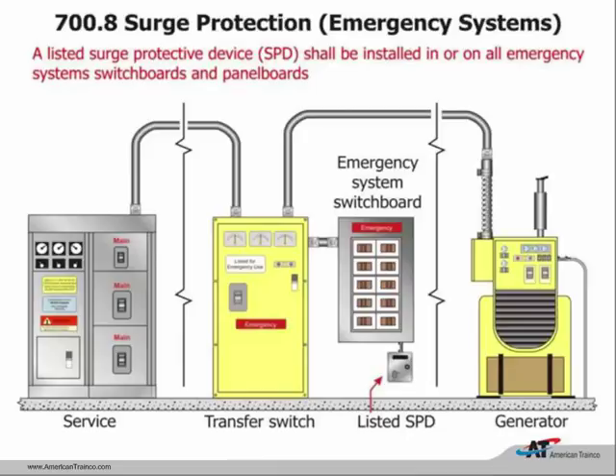Chapter 7 covers emergency systems. A listed surge protector device must now be installed on all emergency system switchboards and panel boards. In a hospital, there's a lot of electronic equipment, and they want to make sure the emergency system is reliable to take care of patients who may be depending on it.